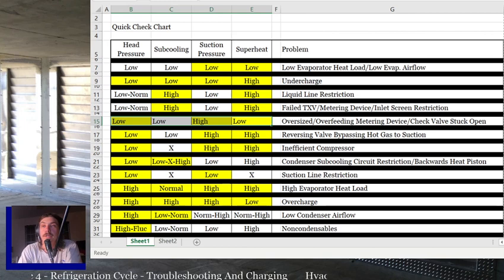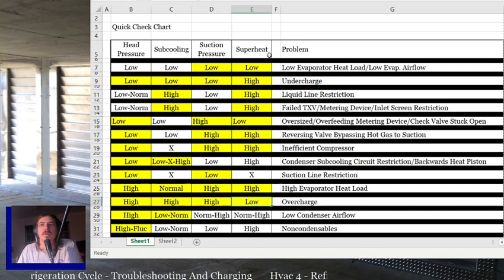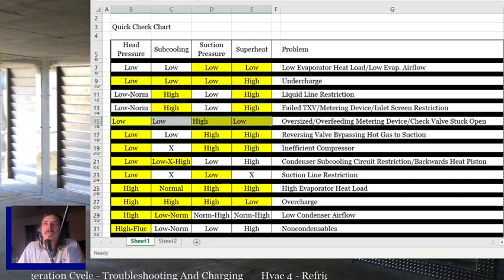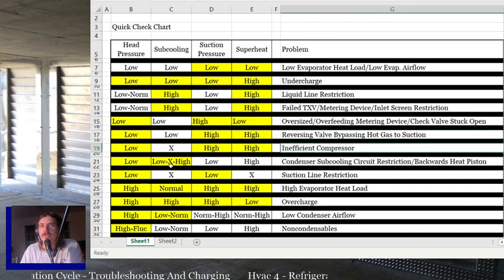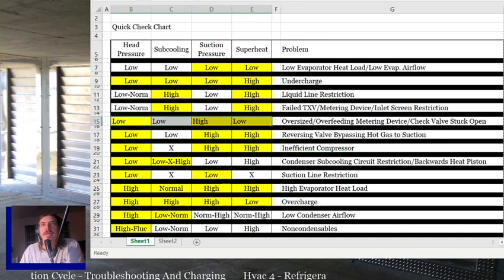That could be low evaporator heat load because it's low airflow. It could be low evaporator heat load because your outdoor unit is way too big for your indoor unit. It could be low evaporator heat load because they set the thermostat at 42 degrees and it's 60 degrees outside. There's a ton of reasons why it could be low evaporator heat load, but low suction pressure, low superheat is always low evaporator heat load. So basically, if you look at these, the combinations are what make them special for the most part. Not all of them are all you need to see to determine if that's the issue, but those are kind of the values that when you see them together, you're going, okay, I've got high suction pressure, high superheat with a low head pressure. I'm talking about a reversing valve or inefficient compressor, because nothing else is going to give me that combination. So that's what the highlight is there for.